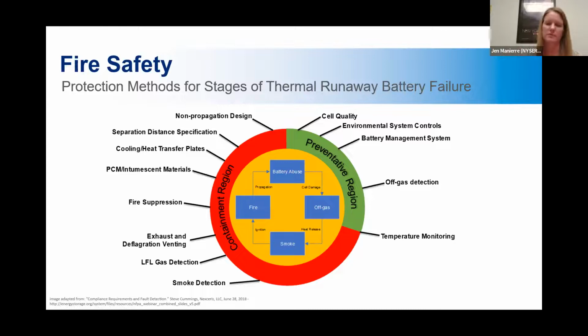All of these things are required in the fire code. Smoke detection, lower flammability limit gas detection. So maybe allowing buildup of some of that flammable off-gassing to a certain point, but once it gets above the lower flammability limit where it could possibly ignite, that could set off an alarm. There's exhaust and deflagration venting features built in so that if the gas is starting to build up, it can trigger an exhaust system that will start exhausting it, or prevent an explosion from happening, basically is what deflagration venting is too.